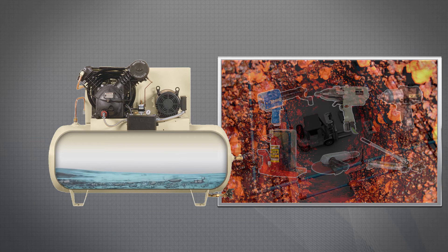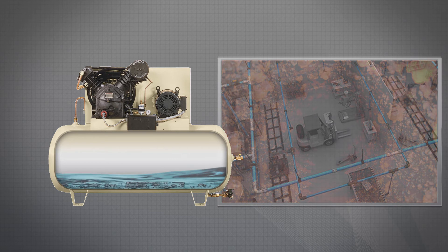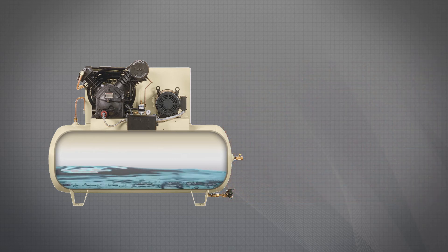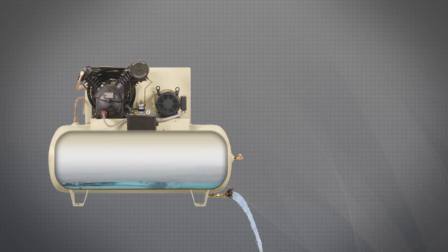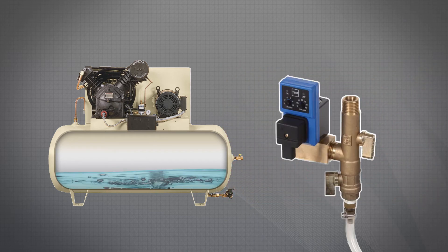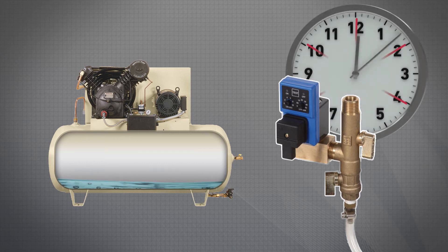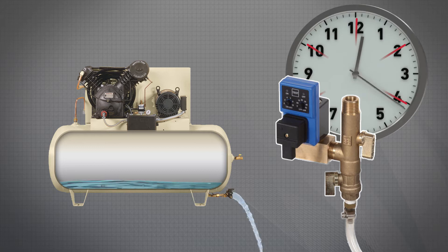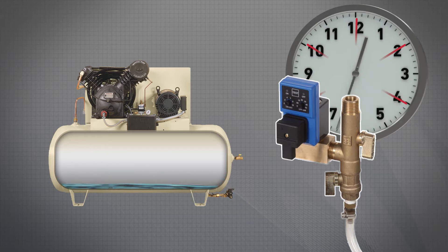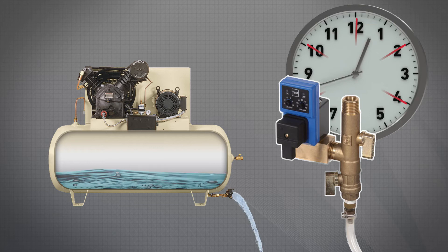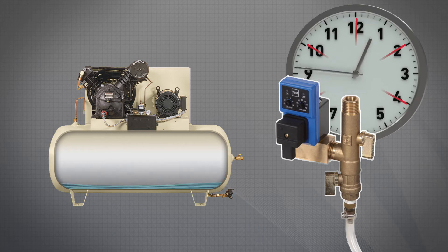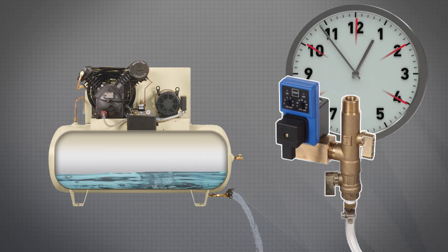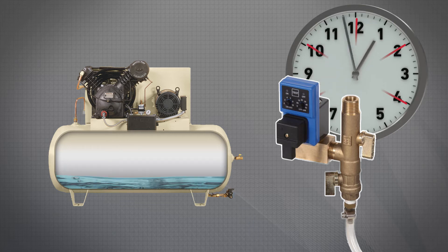Today, the most common way to drain this condensate is through the spigot at the bottom of the expansion tank, controlled with a timed drainage valve set to open for a brief moment at a certain interval. This method is not optimized for either drainage or power consumption, and uses the internal pressure of the system to blindly expel the condensate with no knowledge of the volume that must be removed.